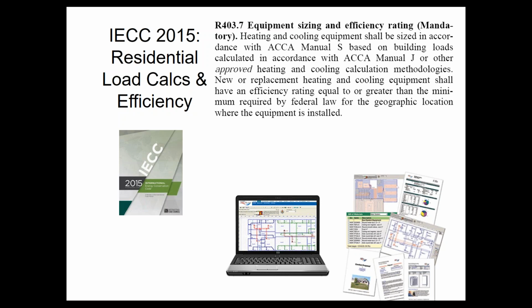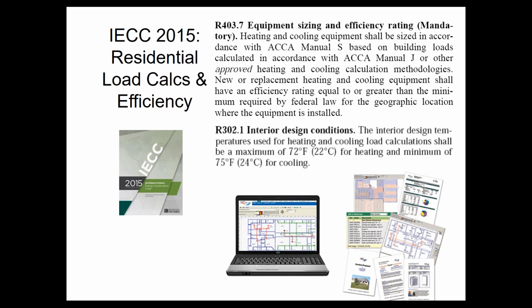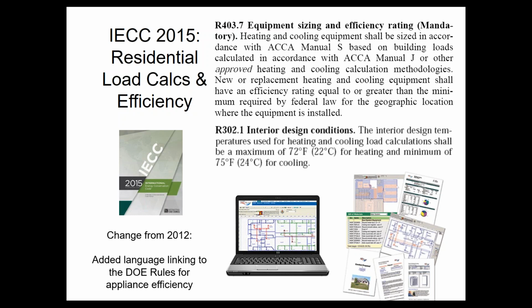That means I have to do both the latent and sensible, cover both of those needs for the cooling system, not just one or not just the total. And it means I can't oversize the cooling system by any more than 15%. That's the maximum oversizing allowed. The code also specifies the indoor temperatures that I must design for. I can design for no higher than 72 on the heating side and no lower than 75 on the cooling side. So you're not legally allowed to size a cooling air conditioner for a 72-degree indoor temperature. That's not allowed. 75 would be the lowest you'd be allowed to do.